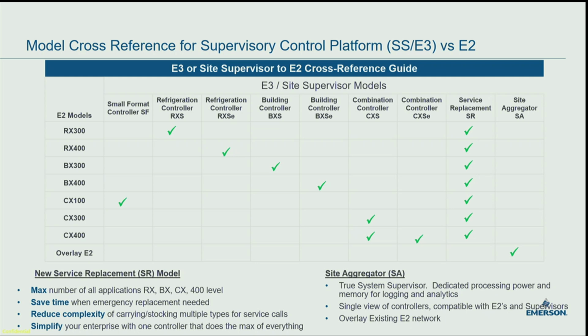So this is just to give you a quick reference between E2 and E3. These are all my E2 models going down the side, the old models, the RXs, BXs, CXs. Across the top is the corresponding E3 or site supervisor model. And you'll see we've added a couple of new ones, mainly the service replacement you'll see on the far right. That one controller would fit every application, so it has the max applications loaded for every controller. If you want one to keep on your truck as a spare or a backup, I would get the service replacement. That way, it doesn't matter if you have a BX, RX, or CX, whatever you may have in the system, you get it tested.